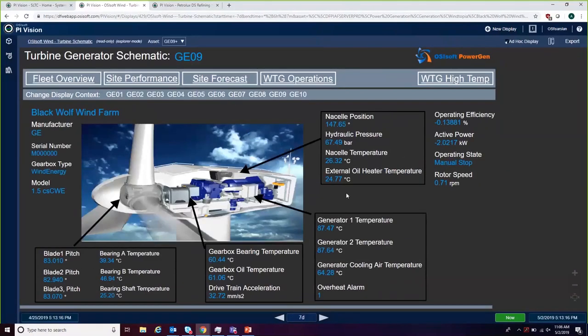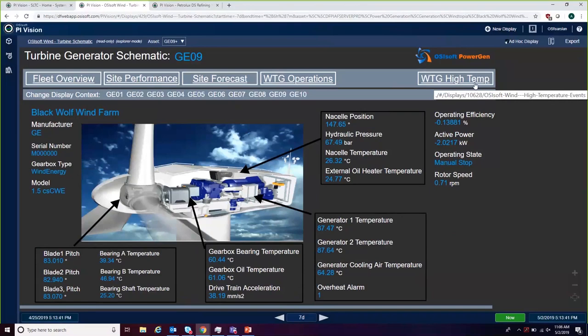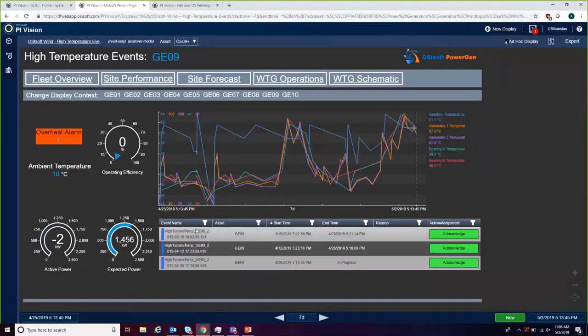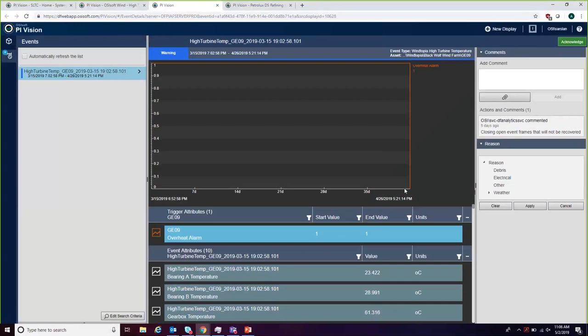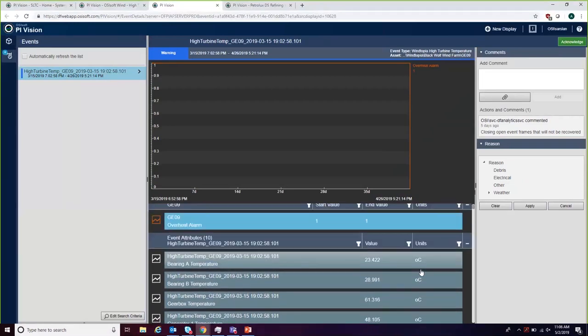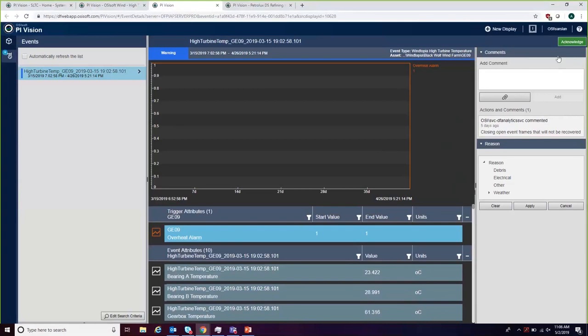I can go to the actual wind turbine details — metadata for the manufacturer, nacelle orientation, the generator heating and cooling, overheat alarms, operating efficiency. Clearly this wind turbine wasn't generating the active power it should be. I can see some of the reasons why: some events have been generated, and specifically one event frame for high wind turbine temperature says something is going on — it's overheating. I can acknowledge it from here so other process engineers know I'm taking a look at it and will send a technician out.